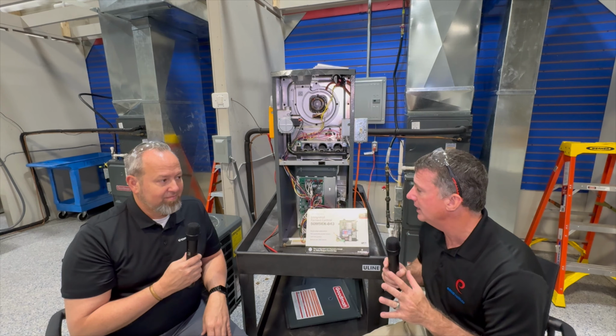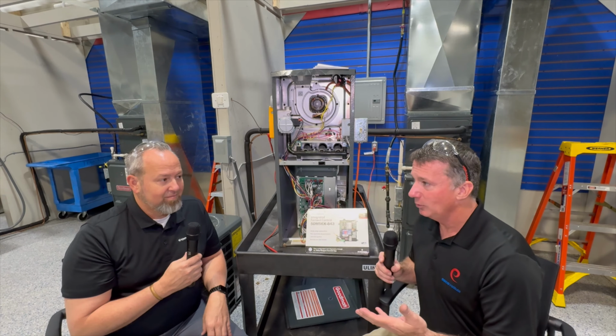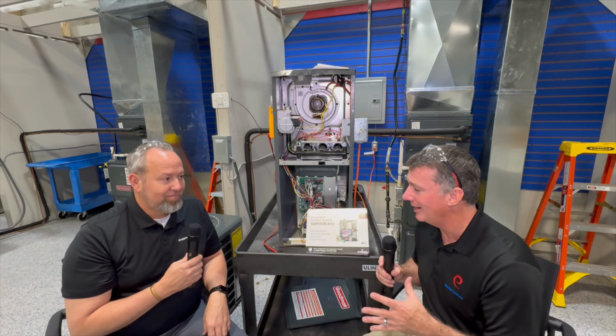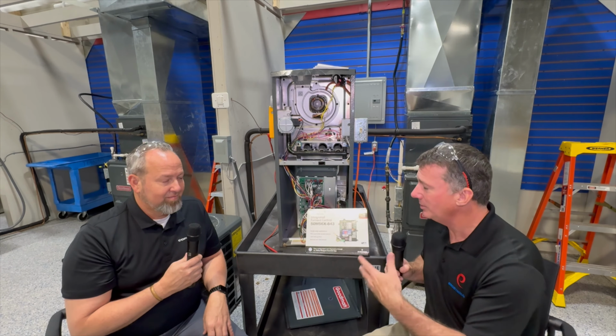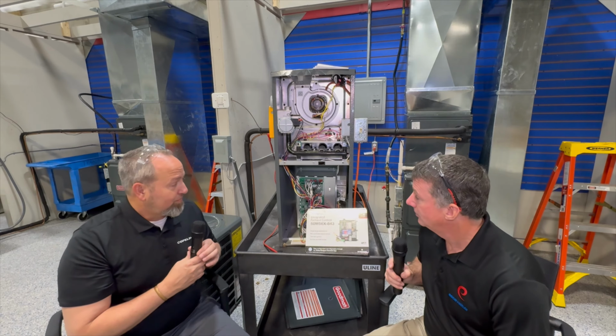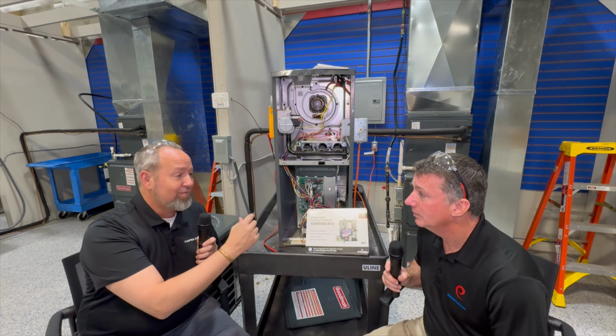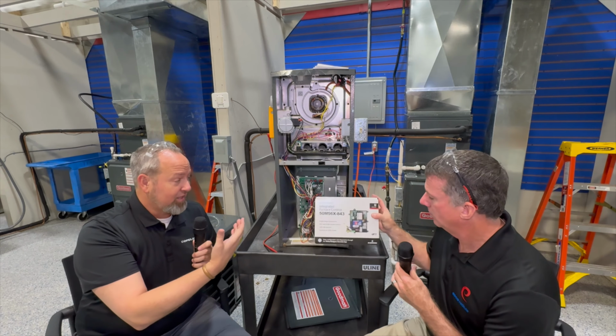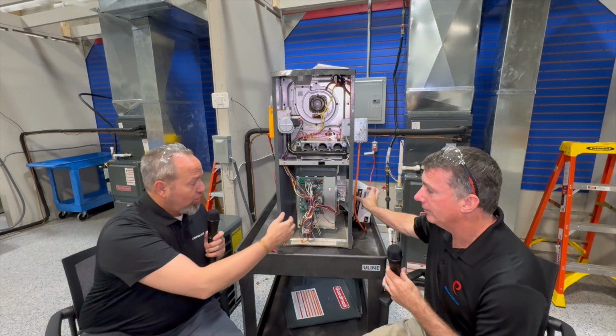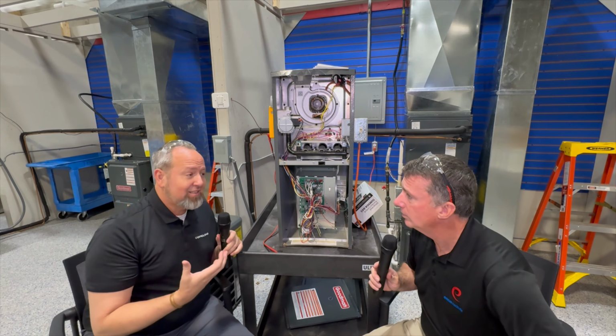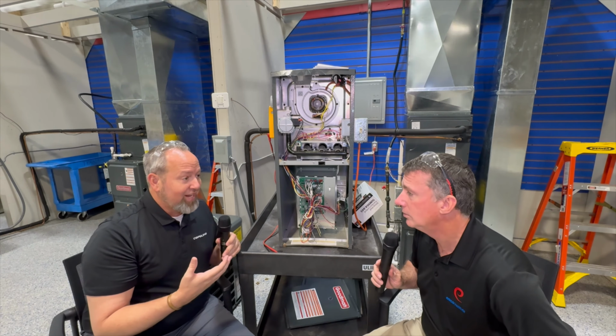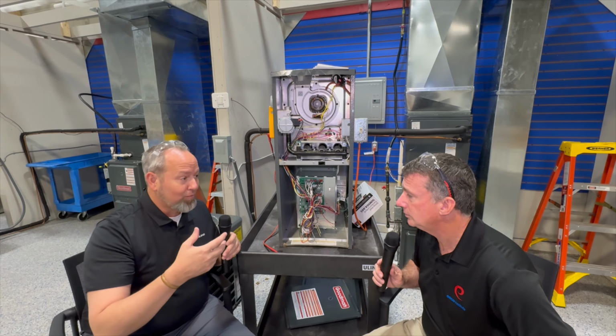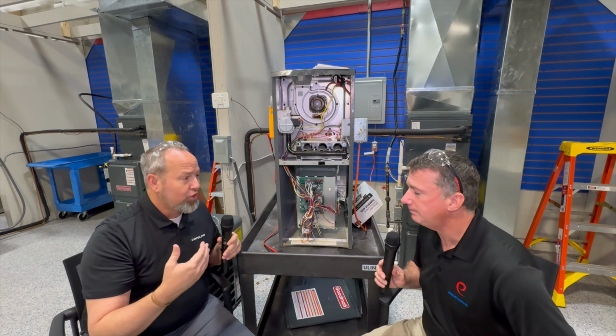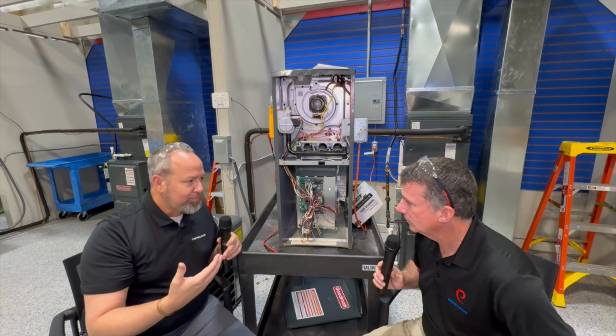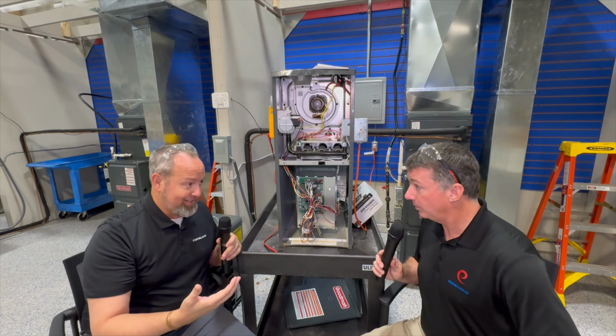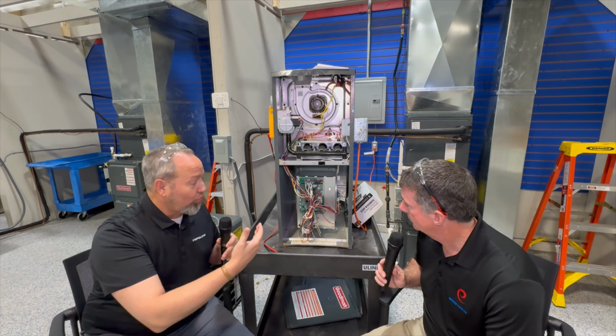Now another interesting thing about this board is that previously we would have a variety of harnesses that we needed to utilize, and that has changed with this board. So tell me a little bit about that. Well, let's start with the pin for that motor. Sure. And one of the additional potentials out there with this inline 6-pin is the fact that some of these motors now will take a voltage signal from multiple pins at the same time. Yeah. So you no longer have a 3 or a 4-speed blower motor. You can have a 9-speed blower motor, and only on 6 wires.